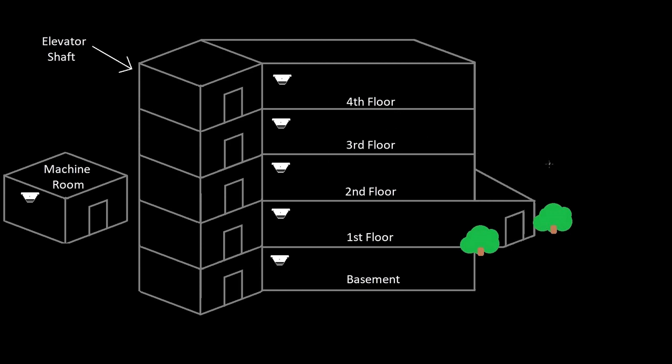You don't want them to go up to the floor of the fire, so the way it works is initially you'll group the detectors into two groups. First group will be all of the smoke detectors outside of the elevator that will send the car to the first floor, and we refer to that as primary recall. Quick little tangent - when you start programming these things and work with elevator companies, in my experience they will often use the opposite term.